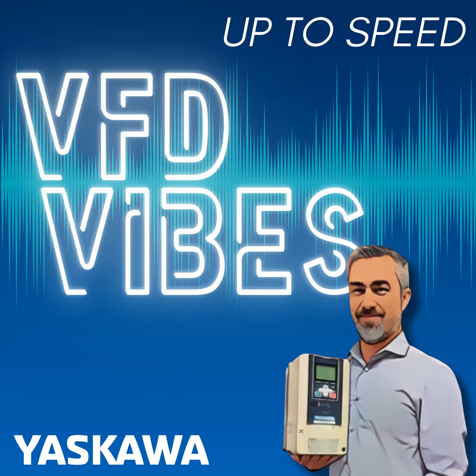So what would happen if somebody either fat fingered or didn't know better and tried to set that accel time to 1 second when it's physically impossible to spin that fan up to maybe 40 hertz in a 1 second time frame? That does happen, and most likely you're going to have an OL2 fault, a drive overload fault. It's probably going to make some wonky noises too for that 1 second while it's trying to start and drawing a tremendous amount of current. And then the drive is going to fault out and basically disconnect output to the motor and sit there and fault. And then you have to troubleshoot it. Yeah, that would make sense.